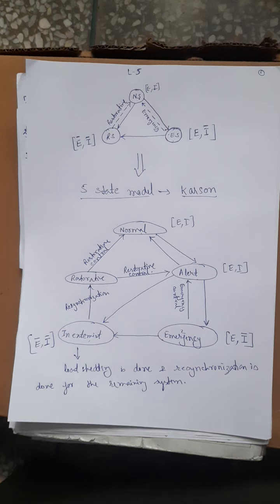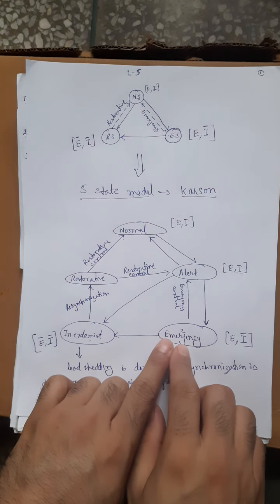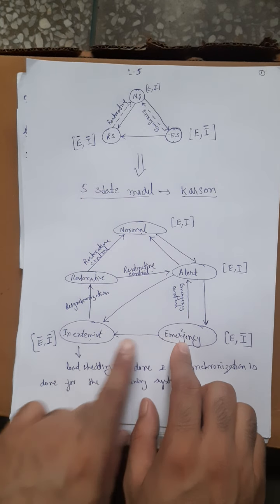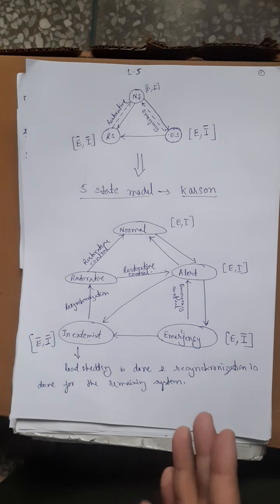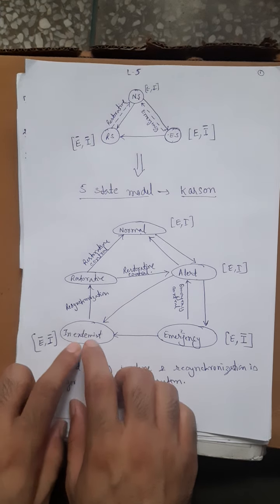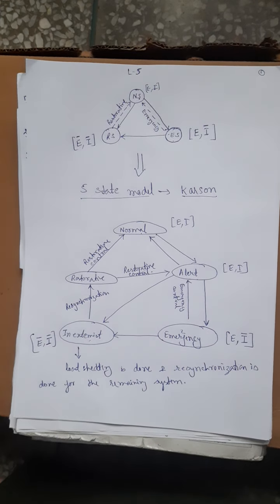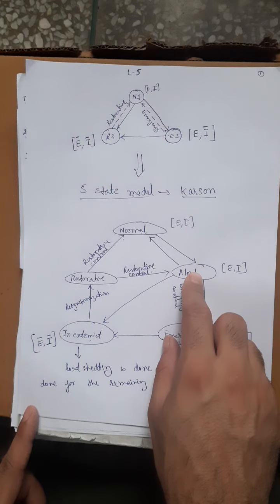Additionally, in the five-state model, from emergency state, the system moves to the extreme state rather than directly to restorative state. Extreme state means many constraints are violated; the system must be resynchronized before returning to the restorative state. This is why the five-state model is more adaptive than the three-state model.